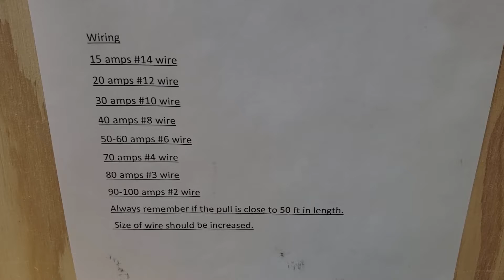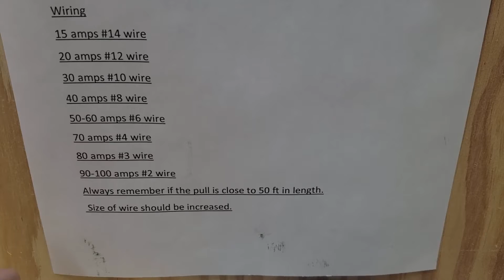And this is just a rule of thumb, so it's good to have with you. I definitely recommend that you write something out for yourself or have a book handy with all the information in there for you. And remember, if it's a certain pull length, over 50 foot, 100 foot, 200 foot, you're going to have factors like voltage drop that you have to account for. So remember that, you've got to make sure you know that, all right?